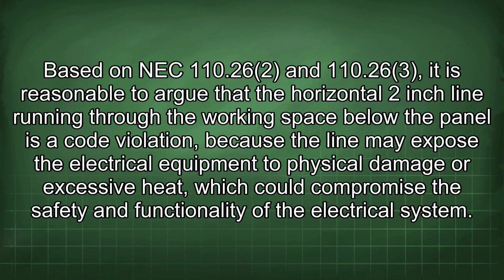110.26 and 110.263, it is reasonable to argue that the horizontal 2-inch line running through the working space below the panel is a code violation because the line may expose the electrical equipment to physical damage or excessive heat, which could compromise the safety and functionality of the electrical system.